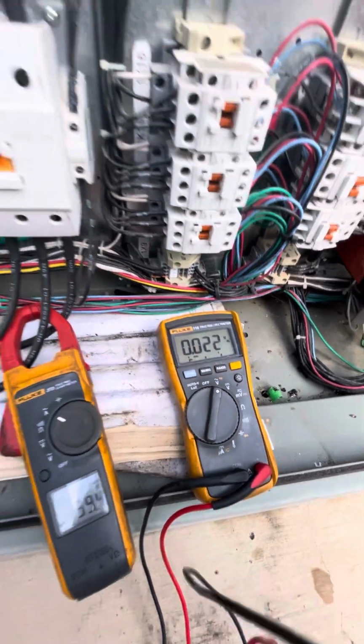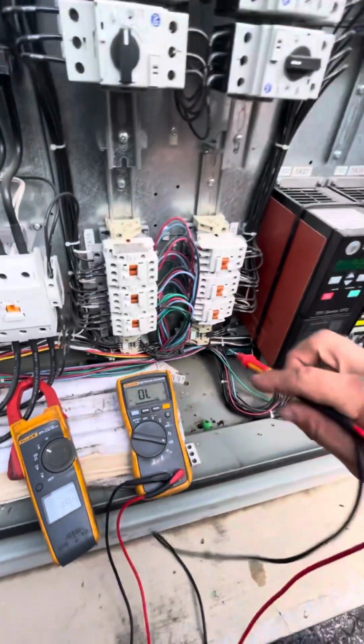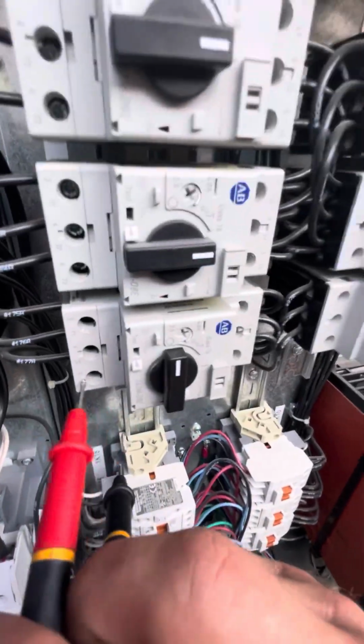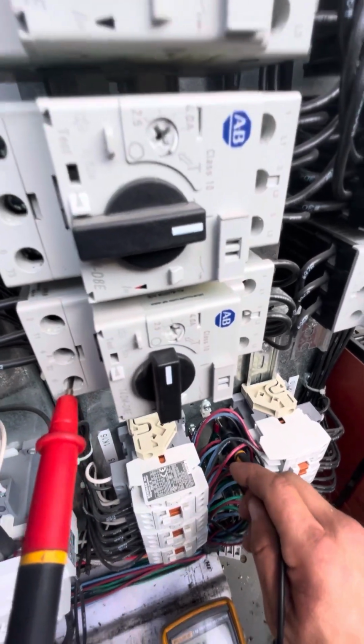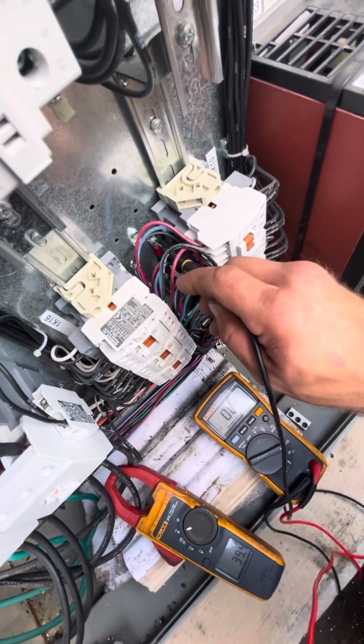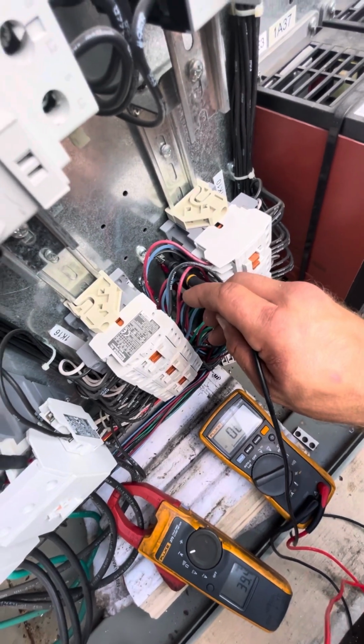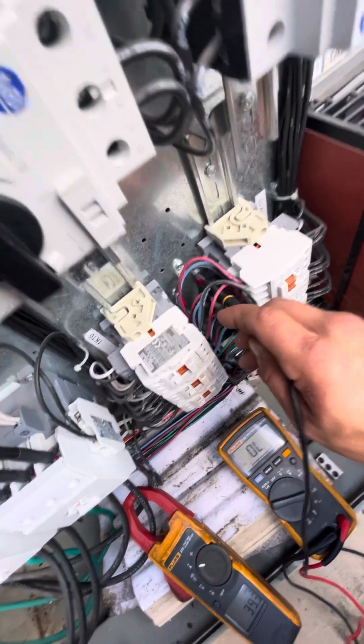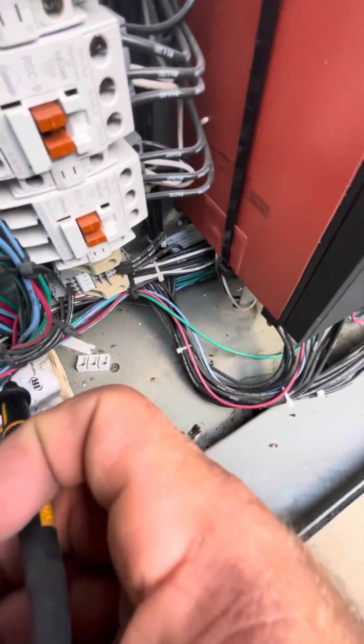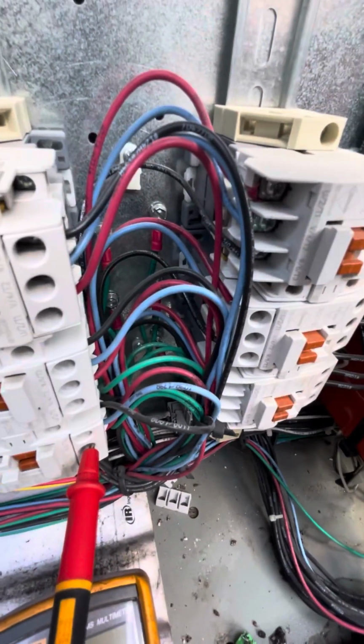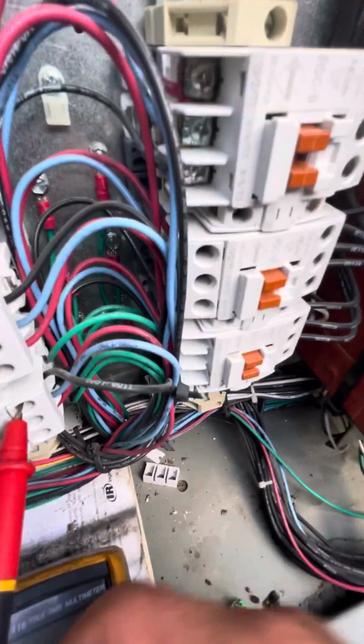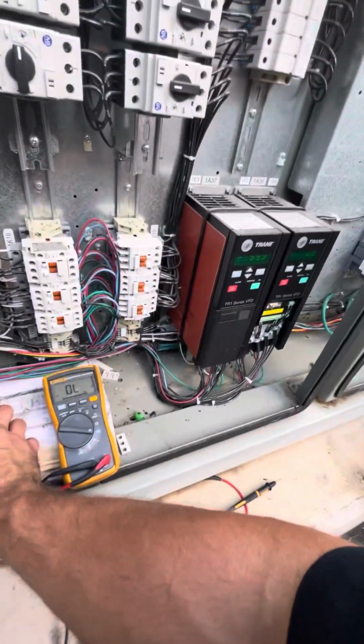Not much. Anyway, nothing's grounded. That's what we're typically looking for. We're looking for shorts to ground, things like that when we see tripped breakers. That is showing grounded. Let's see about here. Well, since it's intermittent, I'm not going to believe it until I see it, because believe it or not, when we apply power to this thing, it'll run and it doesn't trip the breaker.